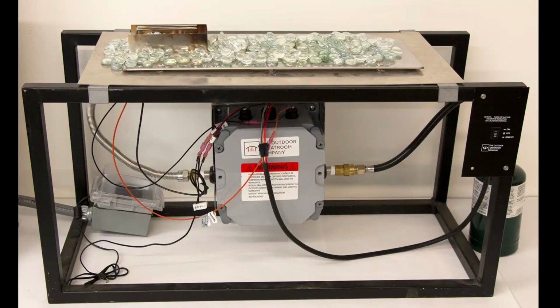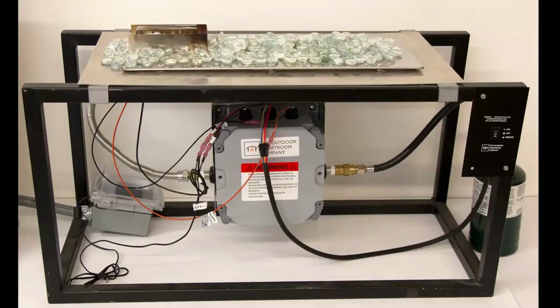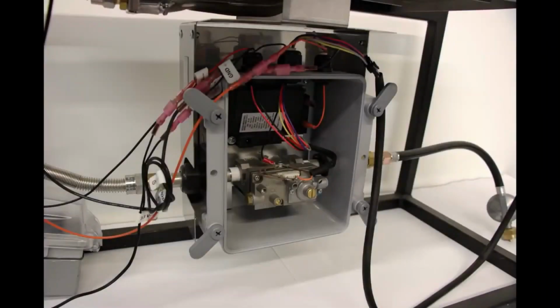So let's get started. Do you hear a beep and a clicking of the sparker? When the burner is turned on, you should hear a single beep from the module and a spark that sounds like this. Note that the beep is coming from the module inside the enclosure and may be difficult to hear, but it is important that you be able to hear this to troubleshoot this system properly. Taking off the enclosure cover may help you hear this more clearly.